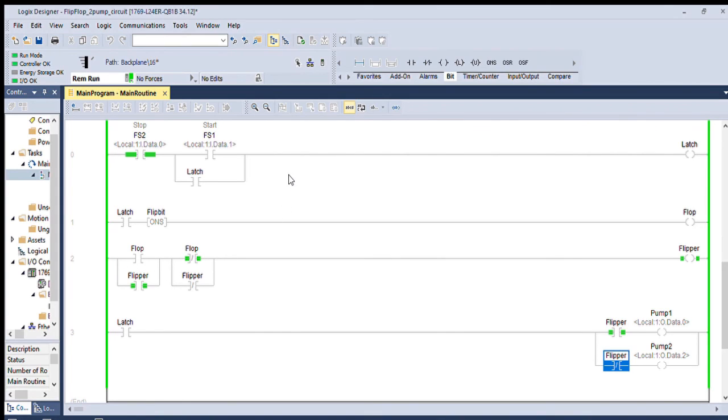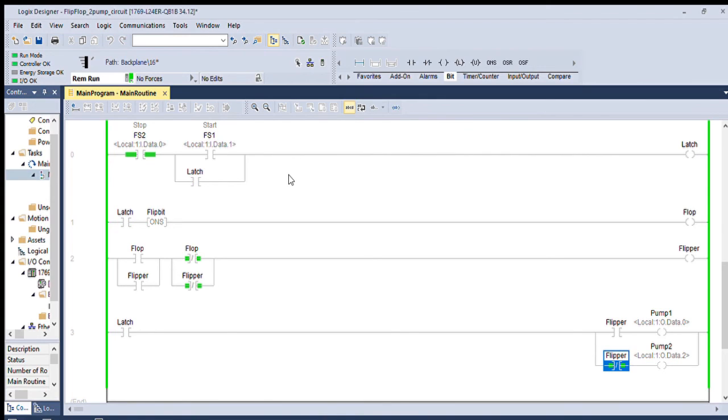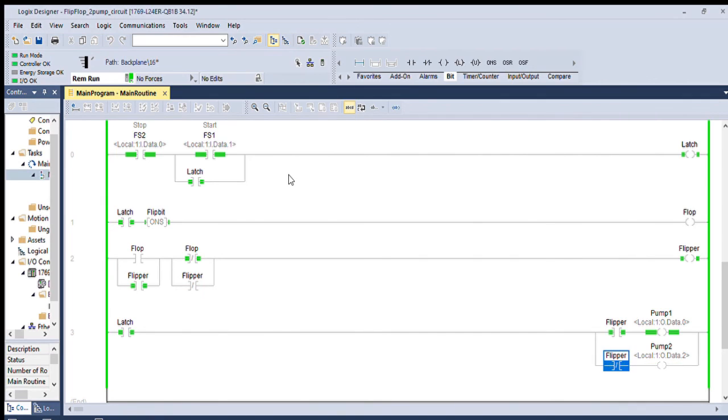And we should have, hopefully, if I did this right, pump two will come on. So now every time I go between a stop start sequence, I will flip and flop between pump one and pump two. And there you have it, your basic flip-flop circuit.